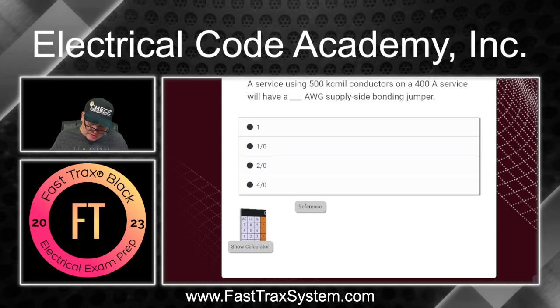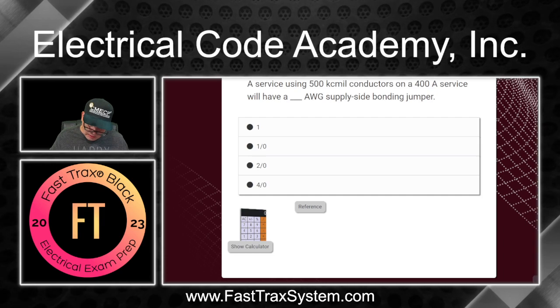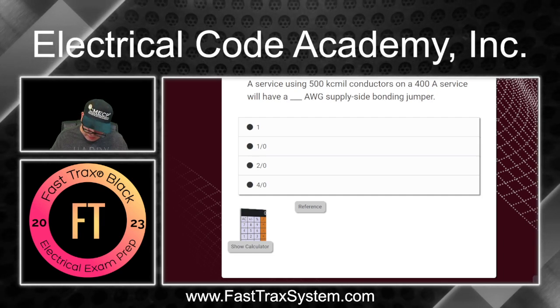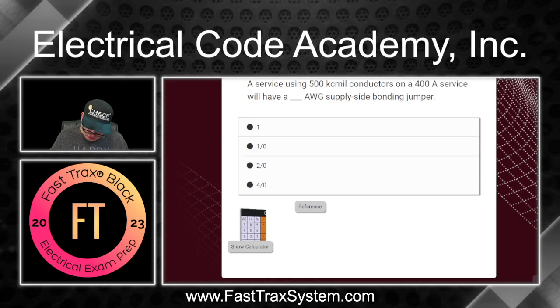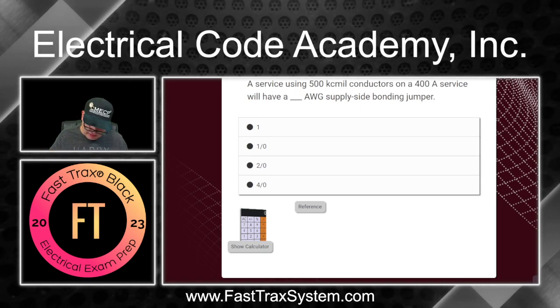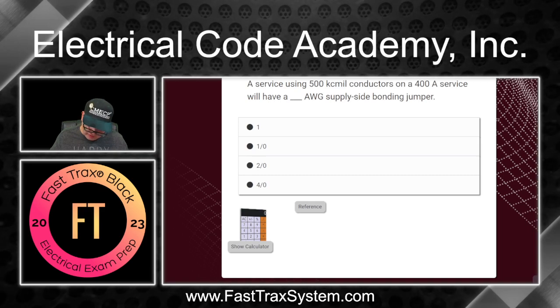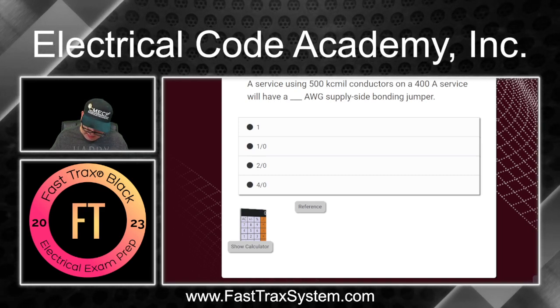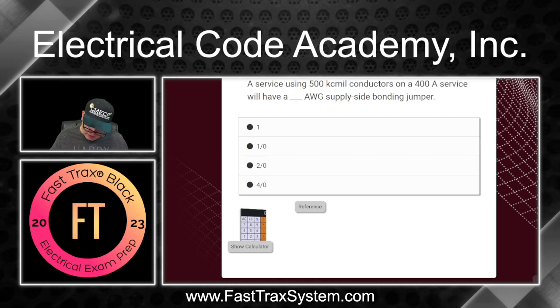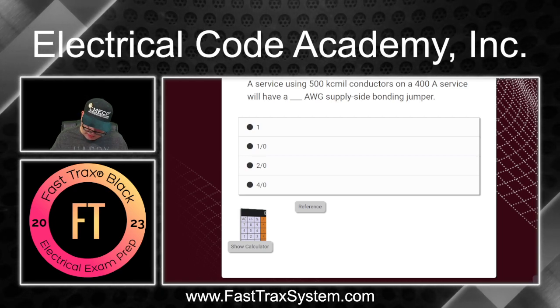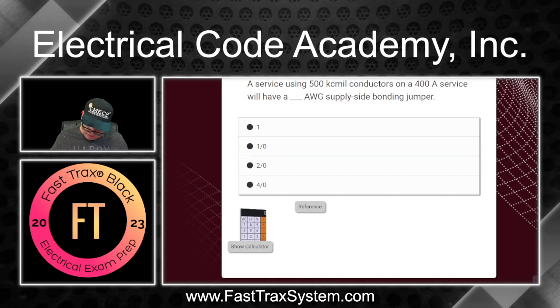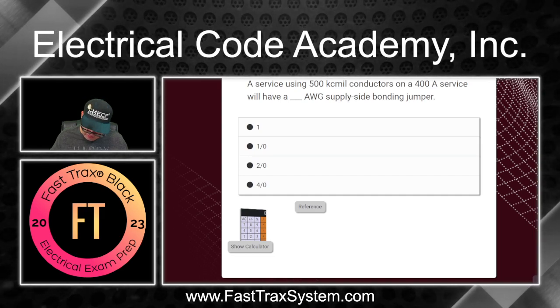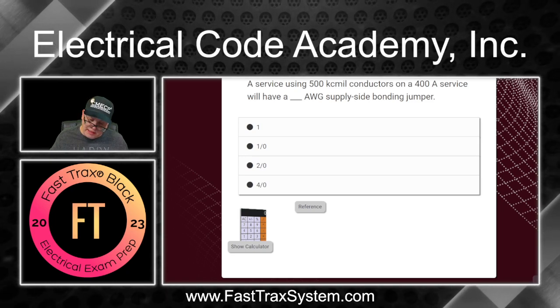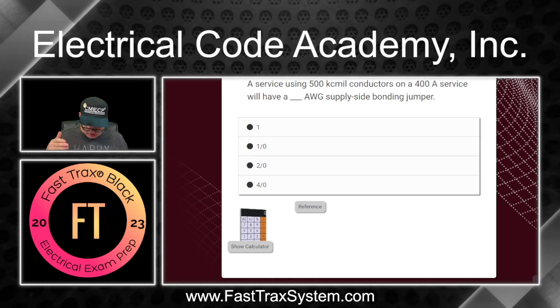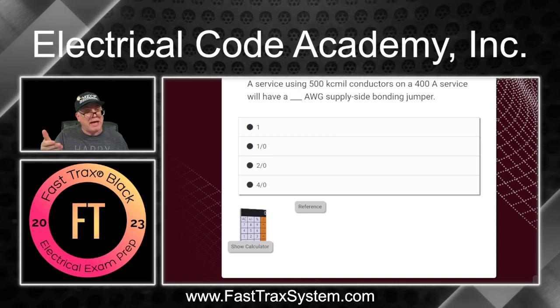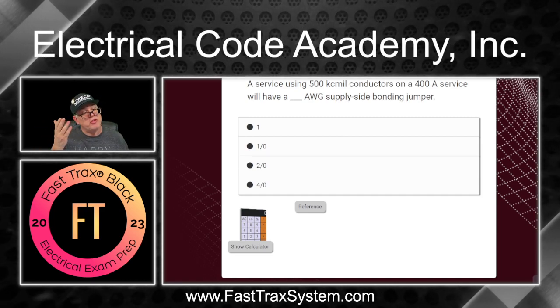Equipment, no. Let's see here. Okay, service equipment. The question was about service equipment. And since we're under bonding jumpers and it says service equipment, it's 250.28. That's going to talk about main bonding jumpers. We see 250.92(B), which says bonding component. And we see 250.102(C). That's where we know that we need to be. So again, that's just one way to find it. I would have gone to services, and knowing what I know, I would have gone to 250.102(C) and gone from there.